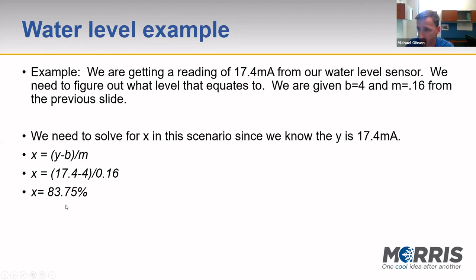So now we know that 17.4 milliamp signal is 83.75%. If I was operating a valve at this point, I would say, okay, that means it's 83.75% open, and then we'd be done. In this situation, we were actually talking about a water level sensor. So what does this mean as far as a water level sensor?